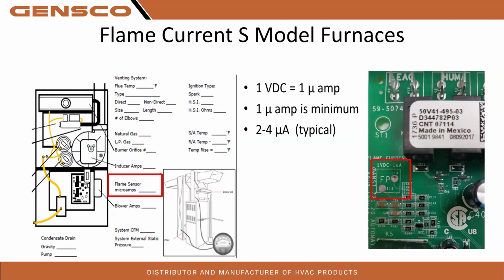We have seen situations where we're getting the voltage and the burner's still blowing out. It happens. We get the call, and of course, we're going to ask you to check for grounds. We're going to ask you to check for high voltage, make sure it's on the correct side and whatnot. But then we're also going to say, make sure you pull the burners and clean them, because everything grounds at the burner. If your burner's dirty or anything there on the transfers, the flame shapers and all that, that can create a problem or feedback to our ground, which would knock out the flame. You would still see the 2 or 4, but it would knock out that ground. So make sure your burners are clean if you're having flame sense problems, especially if you have the voltage required.